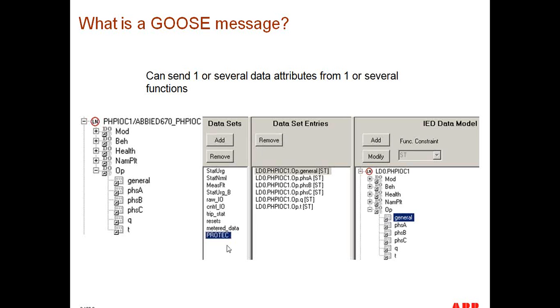So you could send one Goose message with just one piece of information, or one Goose message with several pieces of information. In this particular case, I have a data set with just one data entry, which is the trip data attribute of my PIOC, or protection instantaneous overcurrent, PH for phase. I could have sent the phase segregated signals for phases A, B, and C, quality, and my timestamp. But in this particular case, I just decided to send general, which is the three-phase condition.